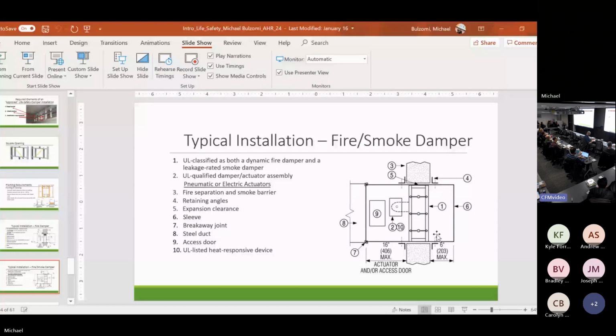So what does that all mean? If I have a 12 by 12 damper, 1 linear foot, 1/8 of an inch, 1/8 of an inch, 1/4 inch minimum. I can make that opening a minimum 12 1/4 by 12 1/4, and then a maximum of 14 1/4 by 14 1/4. Greenheck has plus 2 inch maximum opening. So if I had a 24 by 24 damper, you do the math, I can actually make that opening 28 and change or whatever it comes out to. We don't want to do that, but you can. Sometimes guys cut holes the wrong size. Sometimes they got to move the damper around. You got a little bit of freedom to do that, but you have to cover those openings with retaining angles.